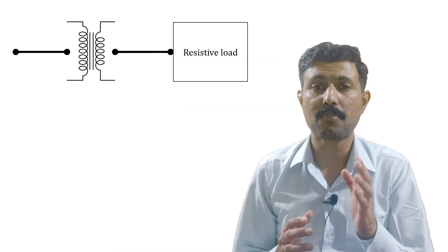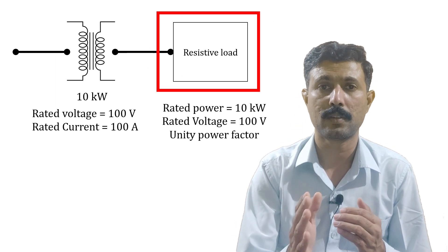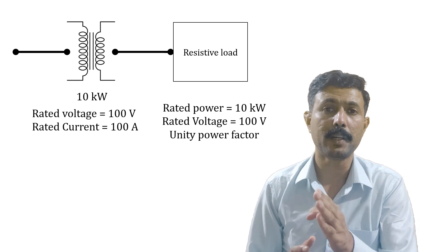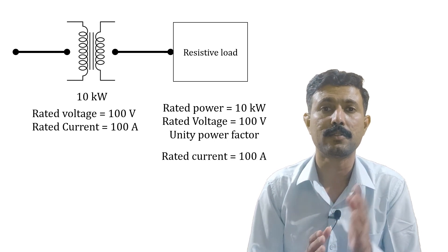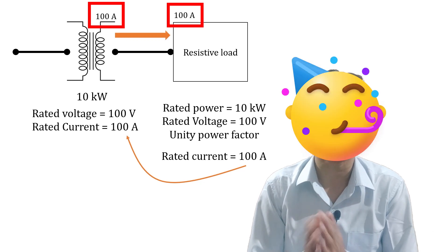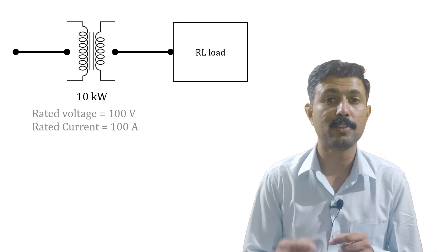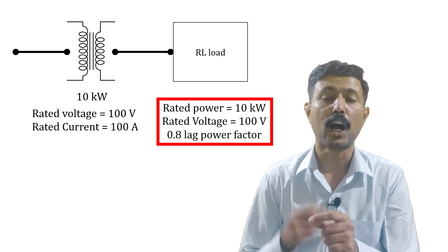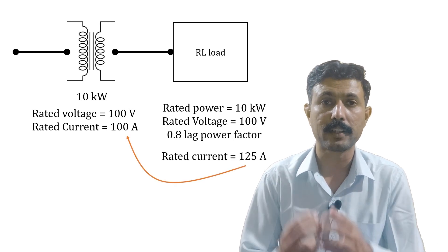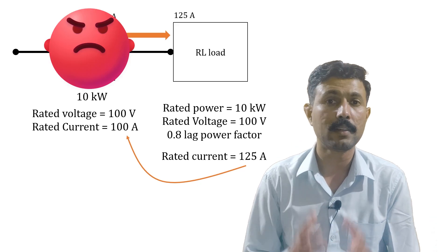Now let's see the disaster that happens if we rate a transformer in kilowatt instead of KVA. Imagine a 10 kilowatt transformer with a rated voltage of 100 V and rated current of 100 A. Connecting a 10 kilowatt resistive load at unity power factor draws exactly 100 A — no problem. But now connect an RL load with a power factor of 0.8. To deliver 10 kilowatt at 100 V and 0.8 power factor, it will draw 125 A of current — but the transformer is rated for only 100 A, so it will burn.